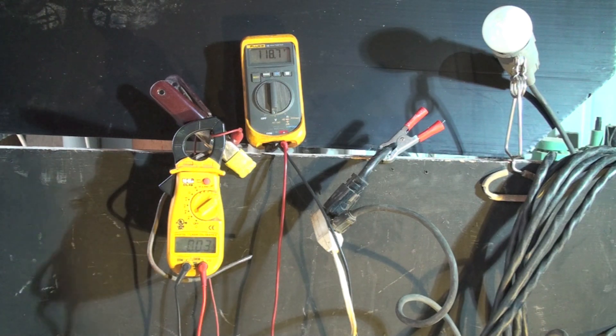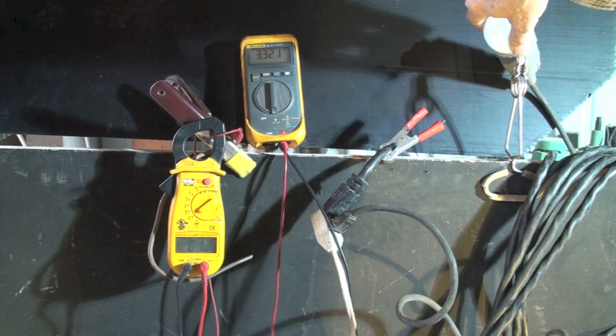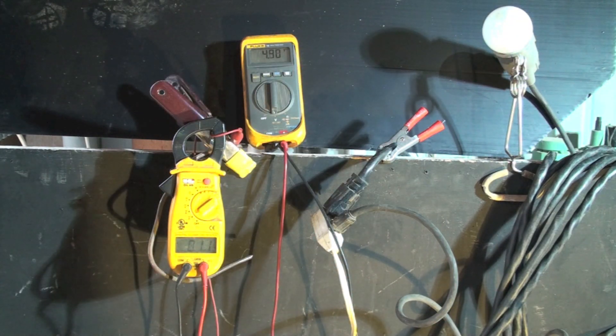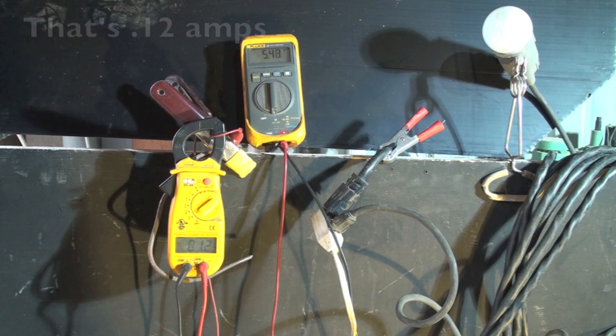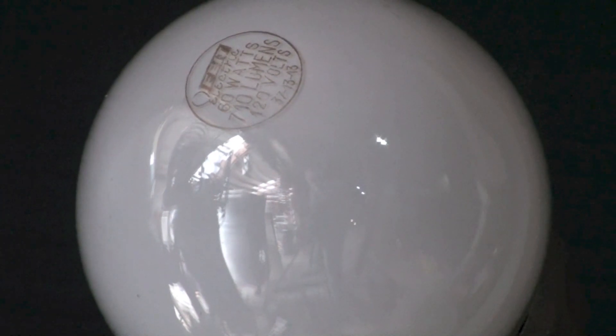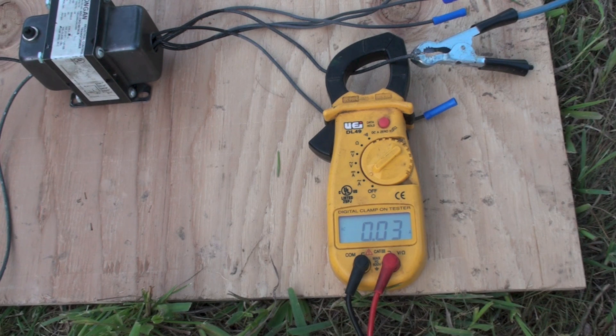The amp probe is reading essentially zero with the circuit open. Now I'm going to turn the light bulb down to where it becomes a load. My voltage dropped to about 5 volts and I have about .12 amps draw. I'll turn off all my other lights to see if there's any glow at all in that bulb. It's a little bright out, but I don't see anything in the bulb — and I shouldn't, with only 5 volts going through it. Let's move on to 240 volts.